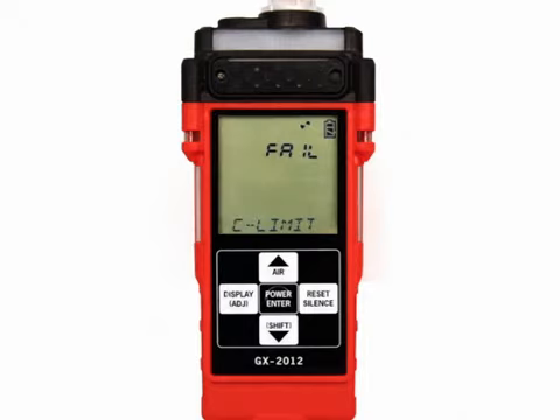You will hear a beep and the startup sequence will continue. If the unit is due for calibration and cal expired is set to can't use, then the fail prompt is displayed. At the same time, the alarm LEDs and buzzer will pulse several times. The fail prompt will remain on the display until the unit is turned off. The GX-2012 cannot be used until a complete calibration has been performed. If calibration is not due or the cal expired is set to no effect, then the display will indicate when the next calibration is due.